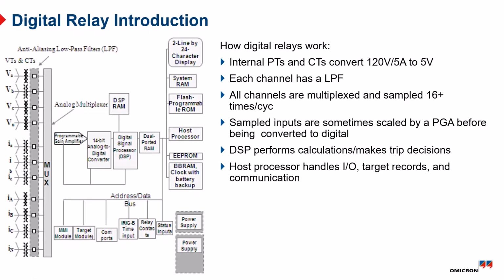Back in these days, for the ADC converters, there was a limitation for the resolution. In this case, it's a 14-bit ADC converter. What that means is that some relay functions measured secondary current in milliamps. Some other relay functions measured secondary current in the 240 amp range. So that represents obviously a huge range of values you have to measure. The designer of the relay, actually a guy named Dr. Yawa, came up with this idea for a programmable gain amplifier. If we're doing a calculation for reverse power where we're looking at a millivolt test, it would use a high gain. And if we're doing a test for, say, instantaneous overcurrent set at 240 amps, they would use a low gain so that the amplitude of the current coming into the ADC converter was in range.